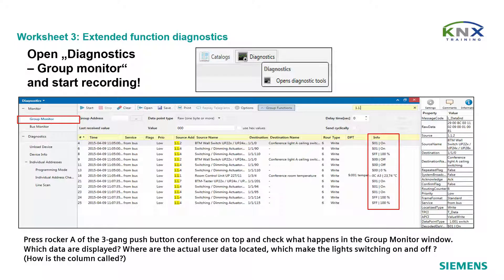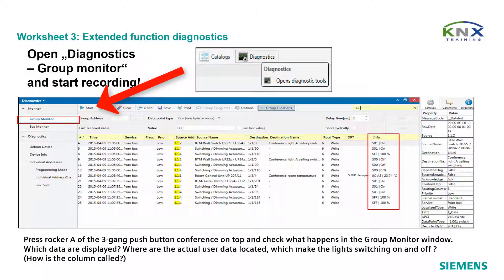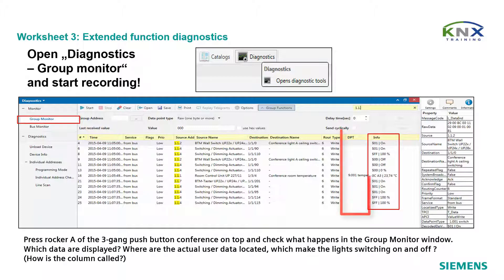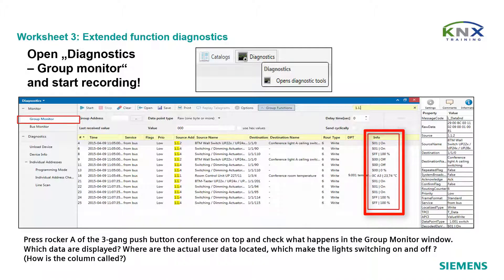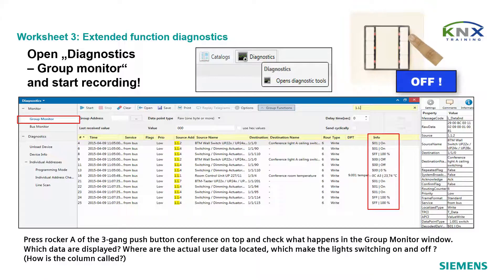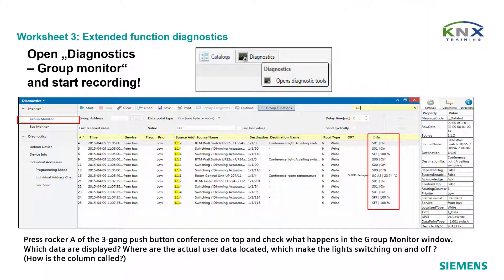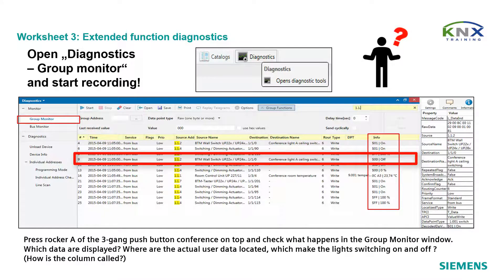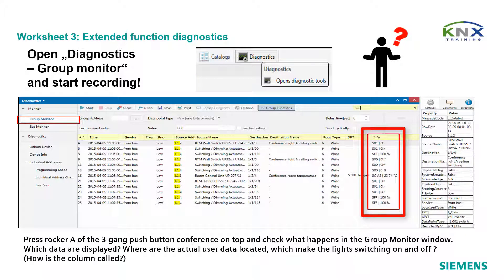Extended function diagnostics. Open diagnostics, group monitor, and start recording. This time we will look more closely at the detail information given in the columns DPT and Info, and at the details in the properties window on the right side for each single telegram. When the group monitor is started, press rocker A of the three-gang push button conference on top and check what happens in the group monitor window. Which data are displayed? Where are the actual user data located — the ones that make the lights switch on and off — and how is that column called?